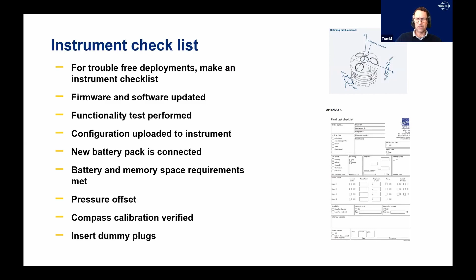Compass calibration is also important. If you are using a tripod or a buoy with metal inside, try to do a compass calibration before going into the field. Also, insert the dummy plugs. We do see people not inserting the dummy plugs, and eventually the instrument will leak.